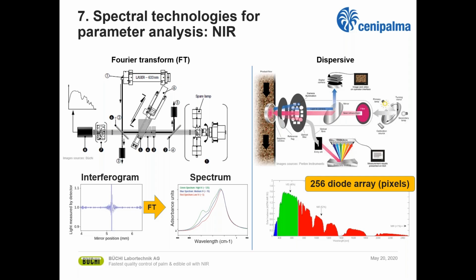On the other hand, in the dispersive technology, the moving detector and the monochromator are replaced by a 256 diode array. In other words, these are the pixels. Each diode of this system can catch a specific intensity in a range of the wavelength.